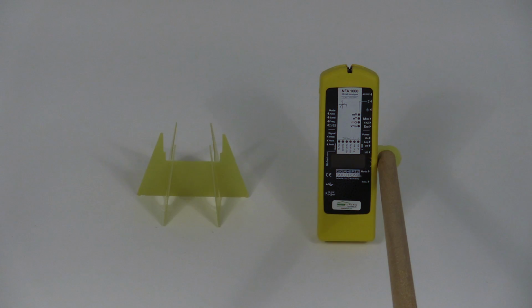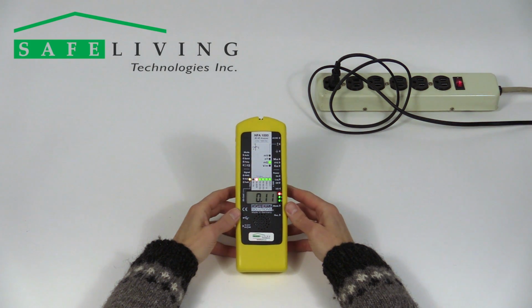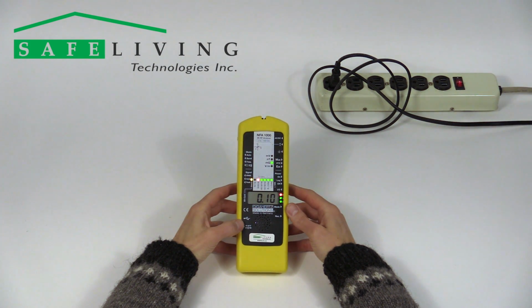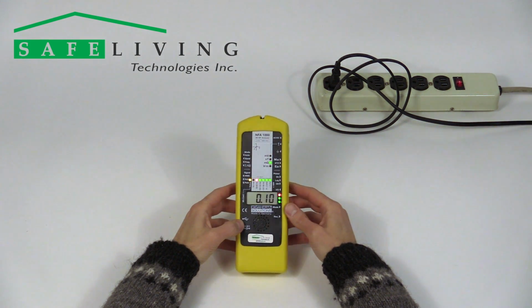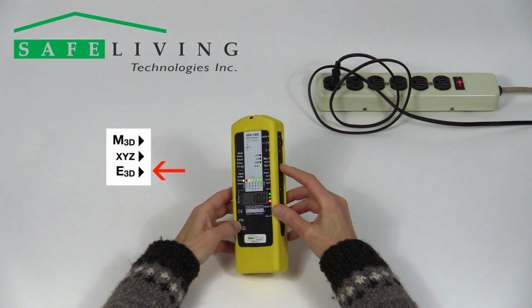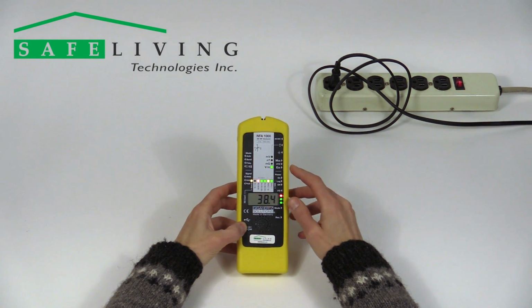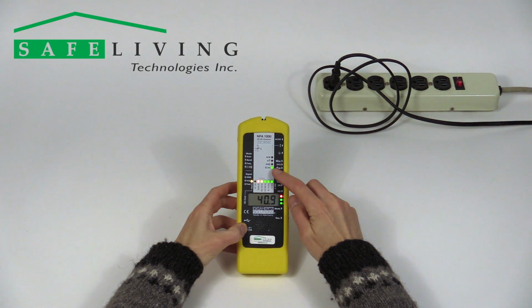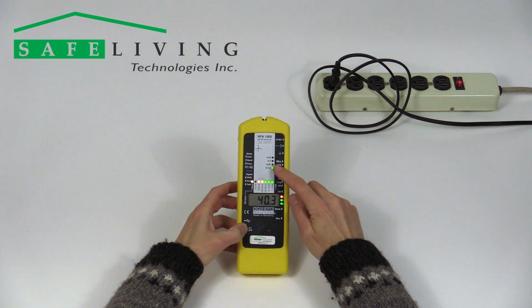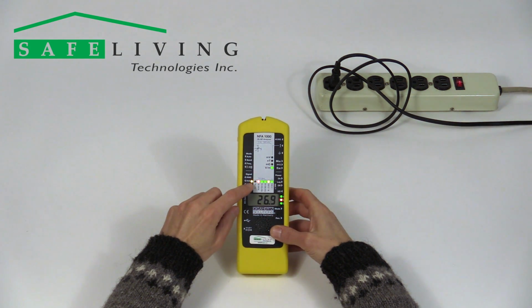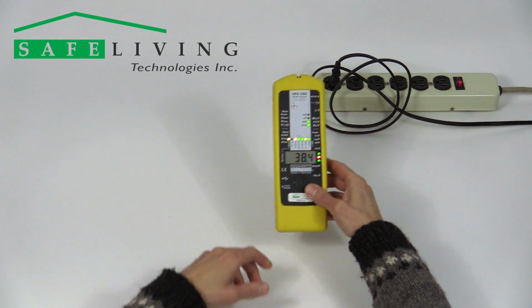To measure total exposure of AC electric fields in its designed potential-free operation, set the field type switch to E3D. Note the solid green light showing that you are now measuring in volts per meter. Note that the LED beside milligauss flashes green every few seconds to indicate that a one-dimensional magnetic field measurement would be measured while logging. Note once again that the status LED is yellow, showing that we are just measuring and not logging data. Move the meter to the location and area of interest.